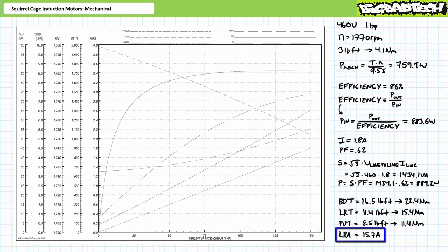Looks like the datasheet specifies this motor will draw a whopping 15.7 amps, 8.7 times the rated current, i.e. more than our 6 times shortcut calculation suggests. We'll examine inrush calculations and the electrical theory of inrush in later lectures. Long story short, all the information is right there on the datasheet.